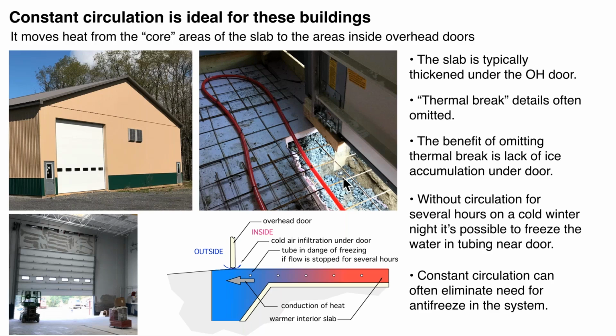So constant circulation, I use the term, it stirs the BTUs within the slab. We have a lot of energy stored in the core area of that slab. And what we want to do is bring some of those BTUs out to the perimeter where these cold spots are, and by doing so, prevent that freezing. So we like constant circulation in these types of buildings because, especially where we have these large overhead doors.